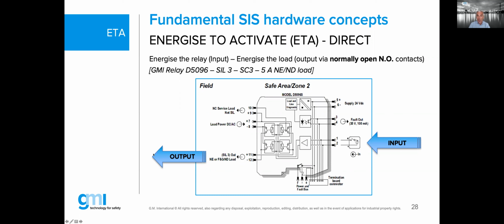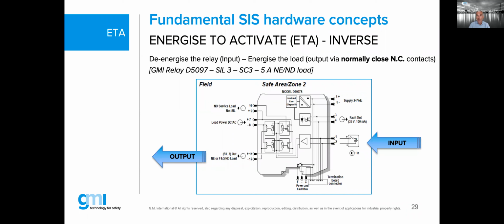Input high, output high, with some smart relay, with some monitoring diagnostics example. Now, assume that I want to reverse this. I want to use an inverse activity. I'm going to use a different relay, and now we are using a relay here with a normally closed contact.